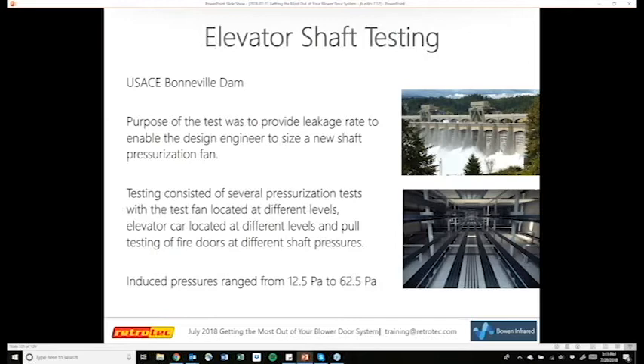Elevator shaft testing, kind of similar to stairwell pressurization. This is just a write-up on a test that was done in the Bonneville Dam. So basically, they needed to have a pressurization fan in the shaft. They needed to find out where that needed to go, where it would perform the best with different levels. And so you can do that with a blower door. You can simulate how that fan would behave and try it in different areas until you get it right, to see where you need to install that fan.